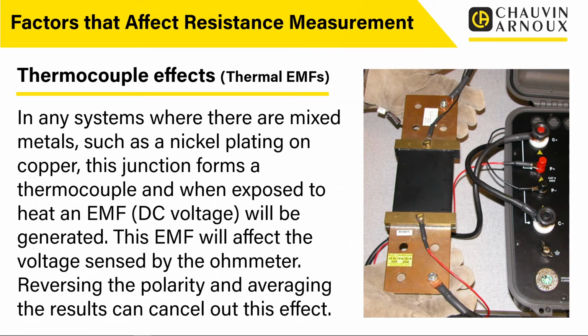Sometimes measurements are even taken at different frequencies and all sorts of things. So it is something to be aware of: if you are carrying out these tests on inductive loads like motor windings, generators, things like that, be aware that the reverse function, which is great for normal resistance to get rid of the thermocouple effects, can cause other issues. So make sure you've read the manufacturer's instructions and you understand exactly what mode to set it on for what you're testing. So that's thermocouple effects.